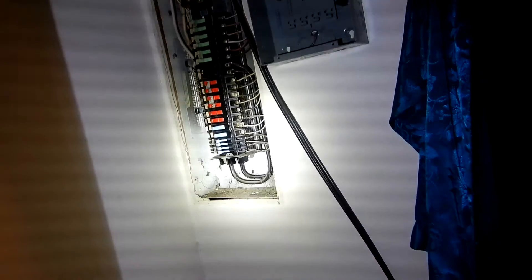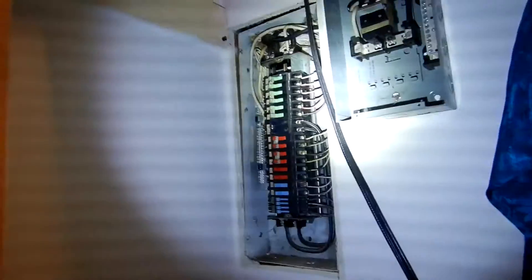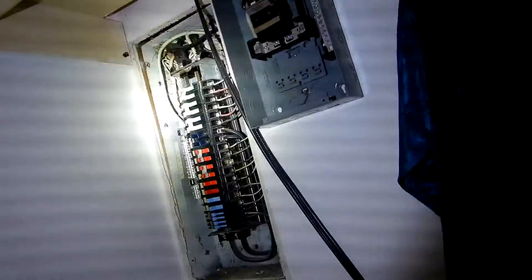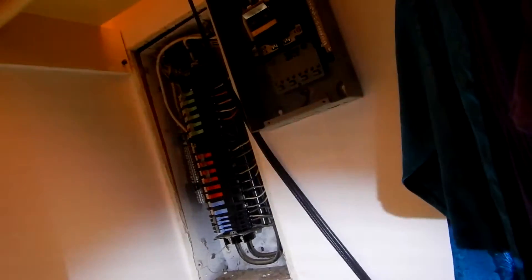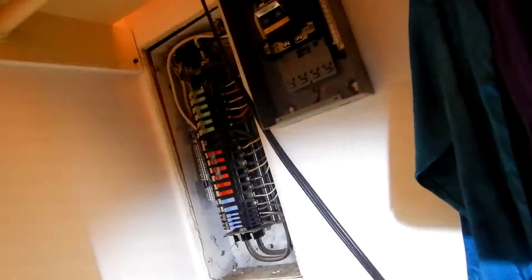We learned we got a Federal Pacific and a Magnetrip Sylvania Zinsco type breaker. We do not have a main single disconnect. We cannot de-energize this system without removing the meter. The meter is not sealed. The electric supply conduit does not extend past the roof covering. We do not have a proper drip loop at the weatherhead.